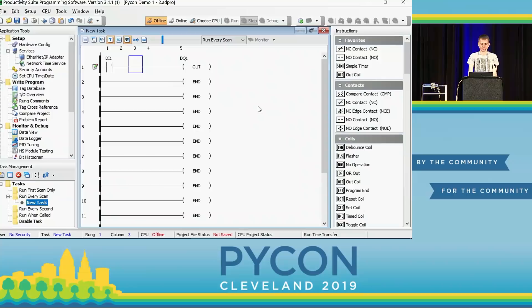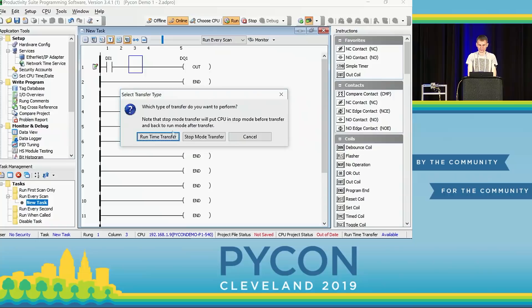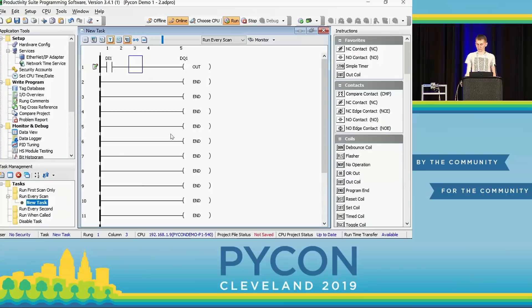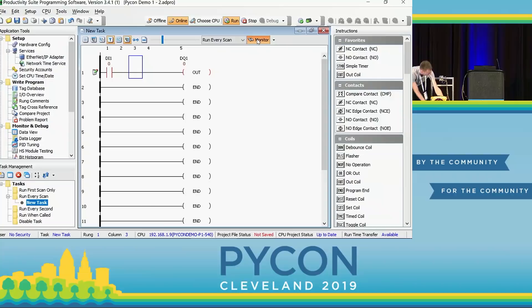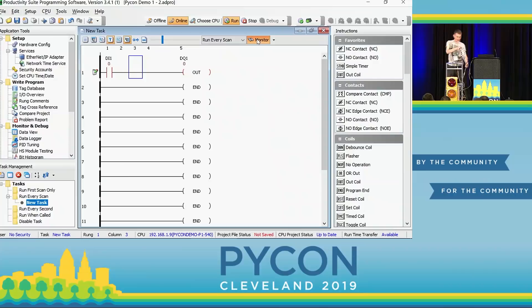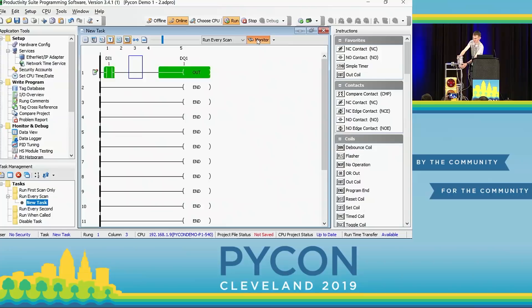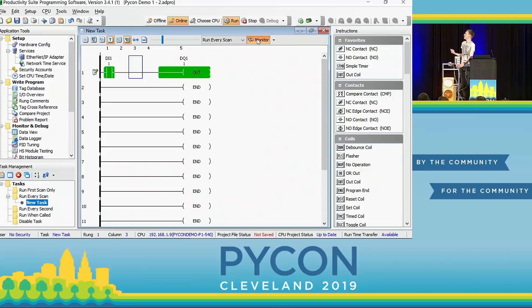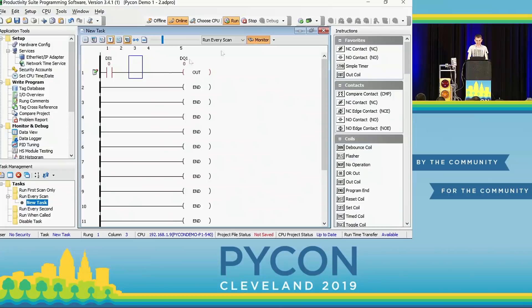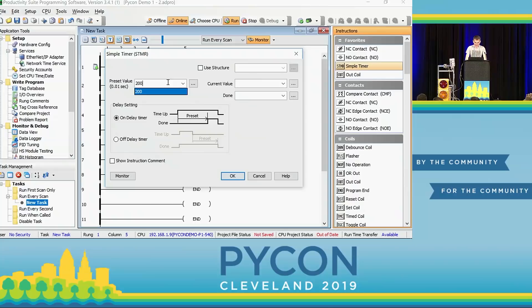I'm going to go online with my PLC — my laptop's connected to the PLC via a network cable for programming. The program is over there now. Press the button: digital input is true, digital output becomes true. I've switched into monitoring mode, so you can see what those variables are doing on screen. Then I add a timer — we want to count up to two seconds, which in this programming language is 200. We give it a variable name for the current value and another for when it's done: timer1_done will be true when the timer finishes counting.